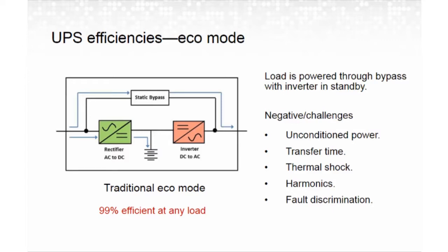Another piece of the UPS is eco mode. This basically is a way to bypass the rectifier inverter. The load is being sent through the static bypass around the inverter rectifier so that you do not have the losses in the inverter rectifier. You can get a UPS up to about 99% efficient this way, but there are some negative effects to doing that. One is unconditioned power. The critical load is being exposed to raw utility power. So if there's any fluctuation in voltage or frequency, it will be seen by the critical load.